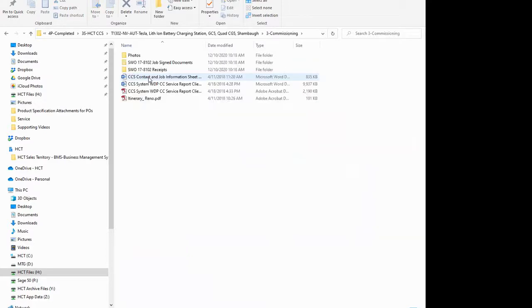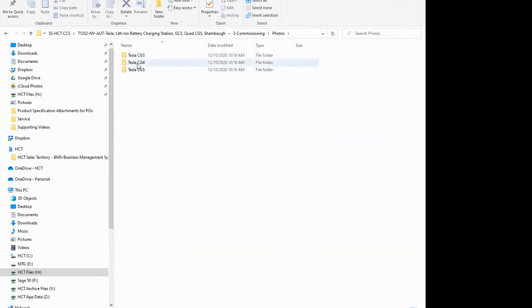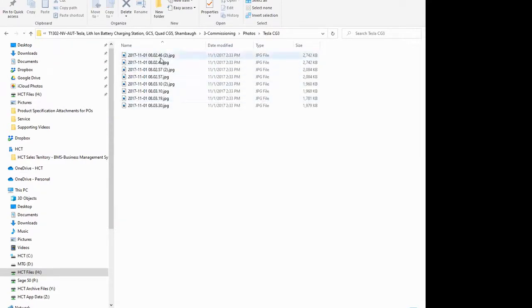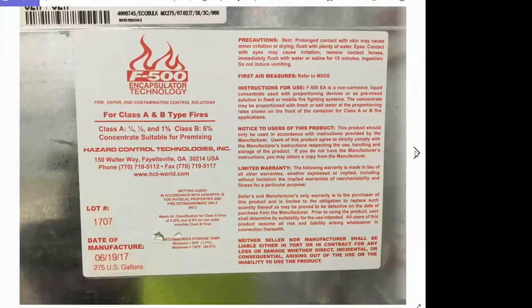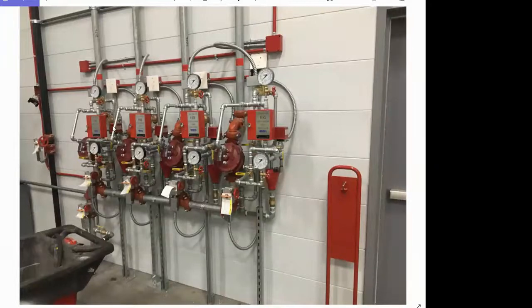When we went out to do the commissioning, hopefully there's the agent. So these are the pipes leading up to the actual charging room, and these charging rooms have 4 racks, if you will. Each rack is 6 high and maybe 50 long, so they're doing close to 300 batteries they're charging in these racks, and they are protected with F500.